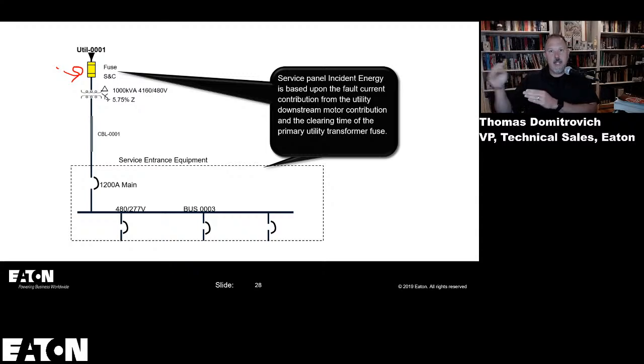You've got to move that instantaneous, add the time delays to let that transformer energize every time it is energized. And what that does is add an intentional delay. And when you think about an arcing fault in this piece of equipment, you're going to rely on that overcurrent protective device, which is not there to protect you in that downstream equipment. It is there to provide protection for that transformer and the conductors on the primary side of that transformer, and it is inflated in size.